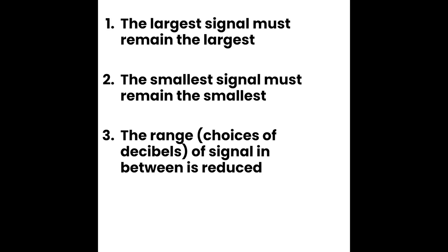The biggest part of these three rules is that when compression is done correctly, no errors will be introduced. We won't have weak signals displayed as strong signals, strong signals as weak signals, or things that should be anechoic being displayed as echogenic, and vice versa. The range is reduced so the machine can process signals correctly during first compression, or we can improve contrast resolution during second compression.